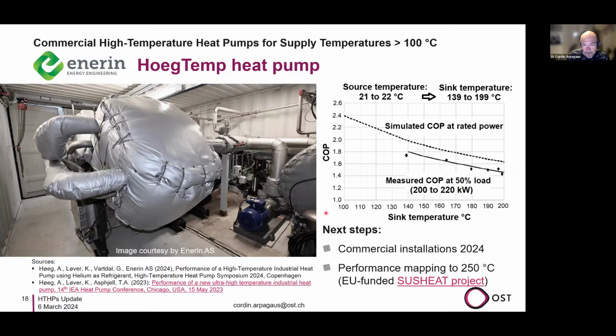On the right, you have some COP data of that system. The advantage of this Stirling heat pump cycle is that it achieves very high temperature lifts from source to sink. So from 21 degrees, let's say, source, to 139 or 199, still a COP between 1.5 and 1.8. So 1.8 times more efficient than an electrical heater.